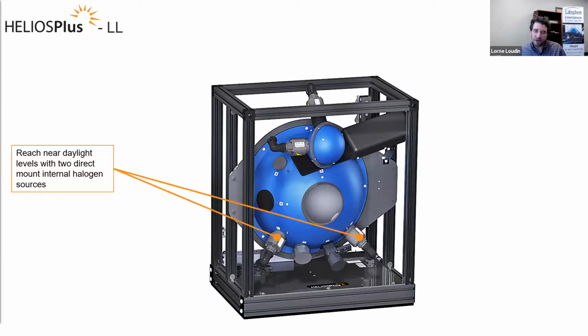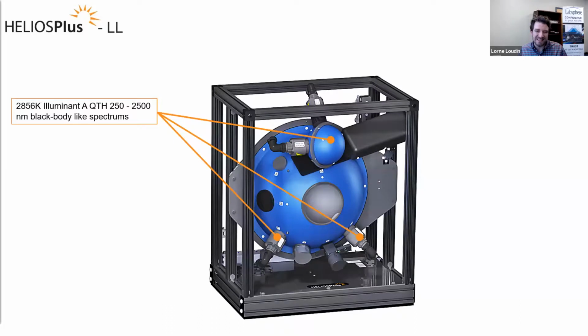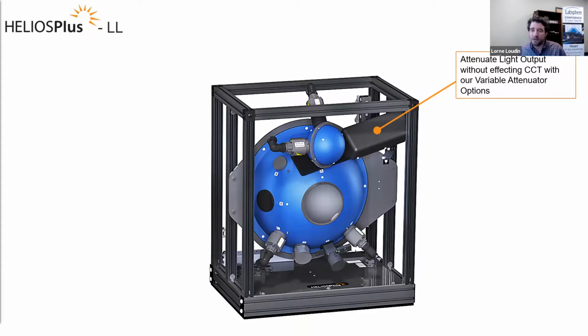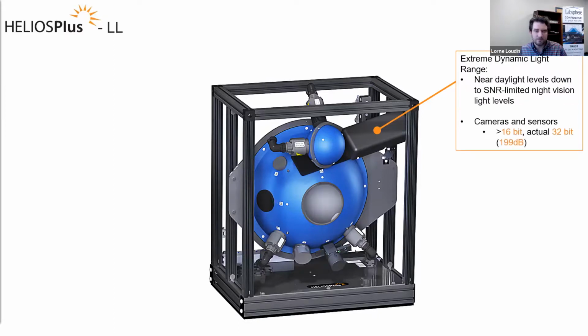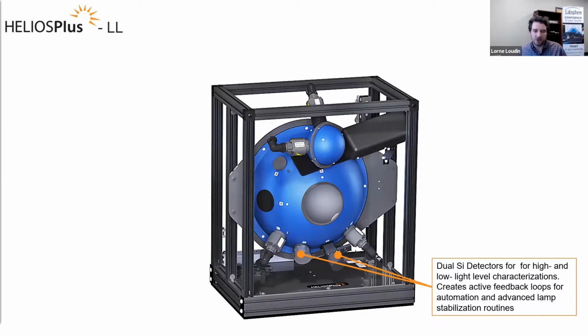And there are some internal halogen lamps down here that will give you the higher end of your dynamic range toward the daylight levels. These can be powered off when you're trying to reach the extremely low light level. This is producing a 2856K illuminant A spectrum. And again, you have a nice variable attenuator to attenuate that light level and change it without affecting its spectral output. The goal here is to go from near daylight levels all the way down towards the noise floor, so you're getting down to SNR-limited night vision light levels. And key here is the dual detector system that allows you to monitor at both ends of your dynamic range.